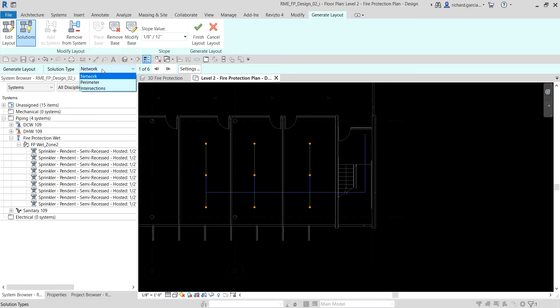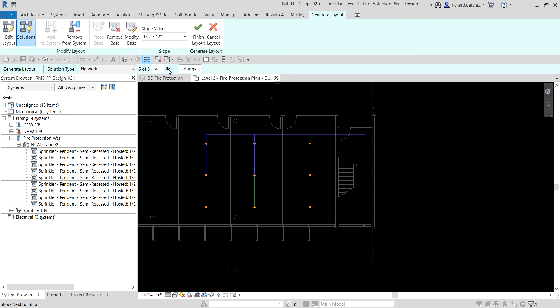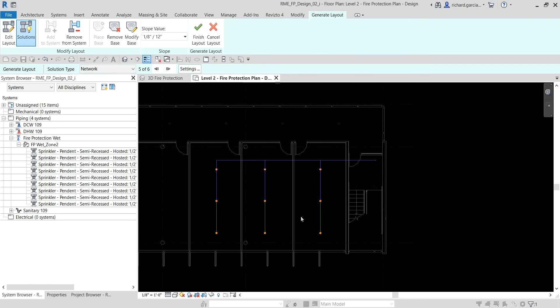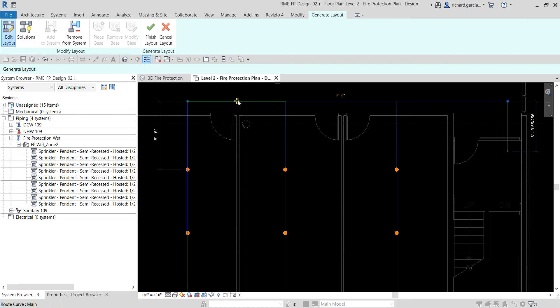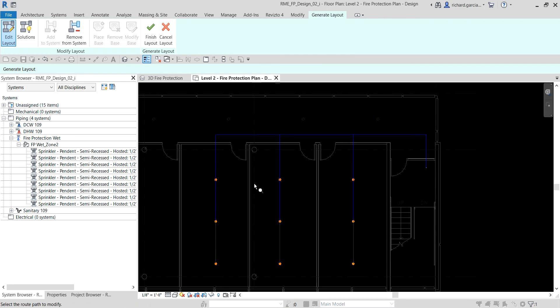Now let's go to the Solution and select from the available options — we have Network, Perimeter, and Intersection. I want to use Network, and within Network there are six solutions. I'll select solution five of six. The blue pipes are the main pipe and the green pipes are the branch pipes. I want to move this main pipe, so I'll click Edit Layout, hold Ctrl to select the relevant pipes, then click and drag the main pipe to the desired position.